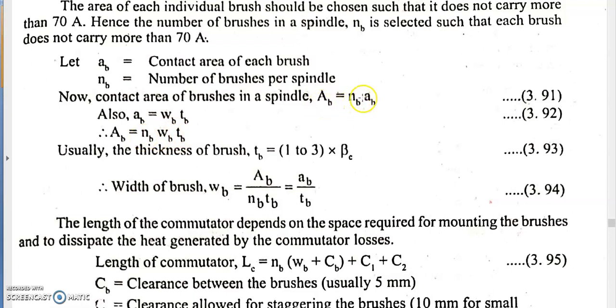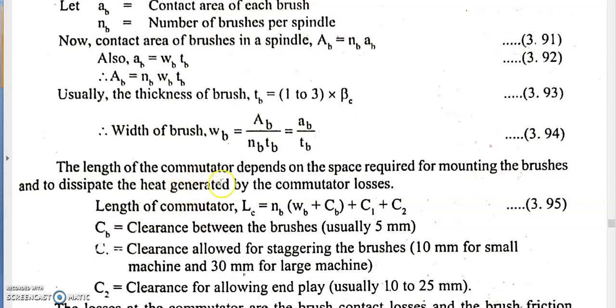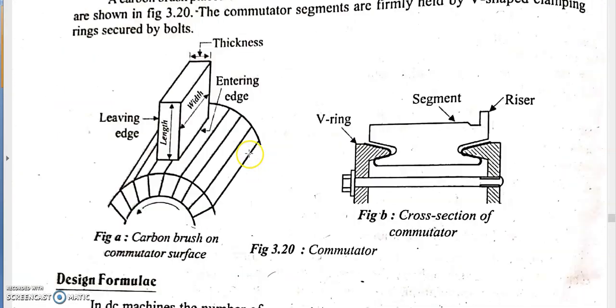Substituting into the equation, AB equals WB × TB, from which we can calculate the width of the brush. The thickness of the brush is 1 to 3 times the commutator segment pitch, given by πDC/C. Since AB is already known from the current and current density, and thickness is known, we can calculate the width of the brush. The brush dimensions include: width of the brush, thickness of the brush, and contact area WB × TB.